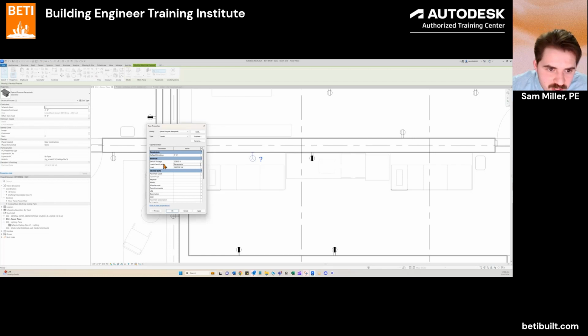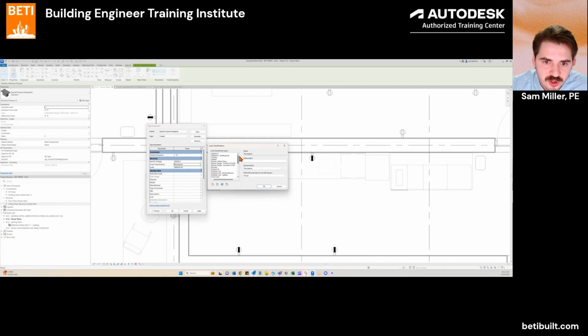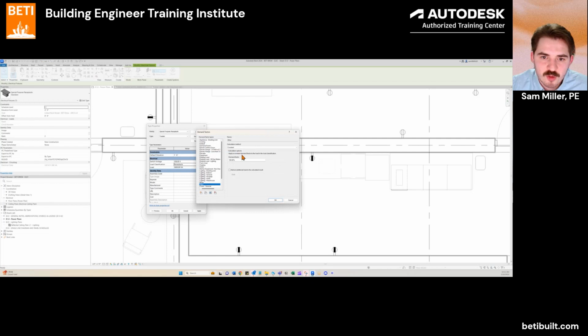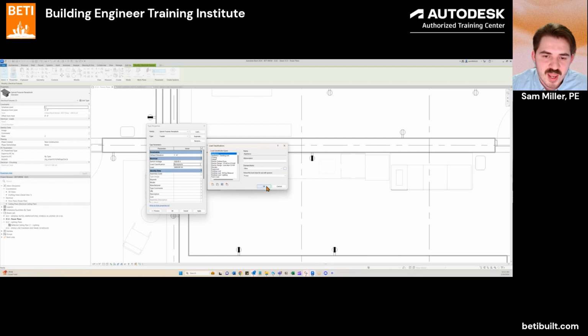So what I do here is go into load classification. I click this little side button, three dots come up, and I can change the load classification. I click appliance. If I want to see what this is actually calculating, I can click the three dots next to demand factor, and it'll tell me what this is using to calculate. This is just going to be 100%, so it'll take 100% demand of this 3600 load.